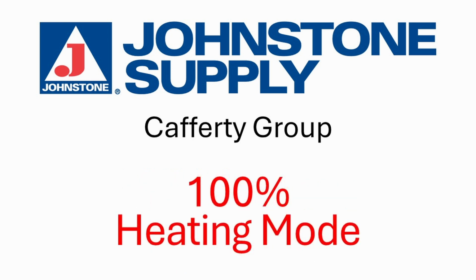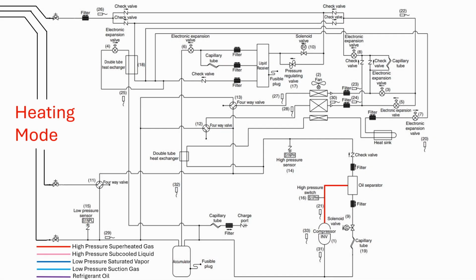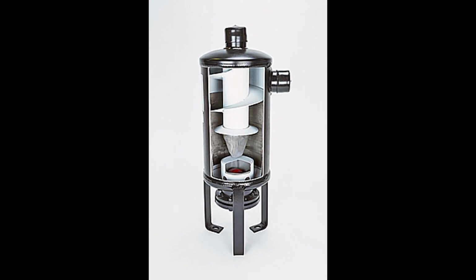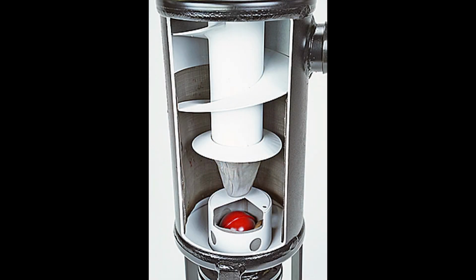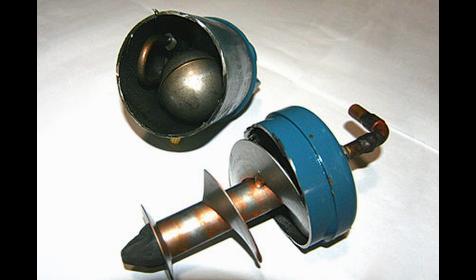This system is in 100% heating mode. The refrigerant leaves the compressor as a superheated high-pressure vapor. Its first stop is the oil separator. The oil separator is a spiral device that uses centrifugal force to separate the oil from the refrigerant as it leaves the compressor. Then it returns the oil back to the compressor where it belongs.